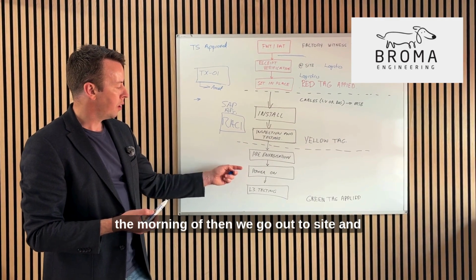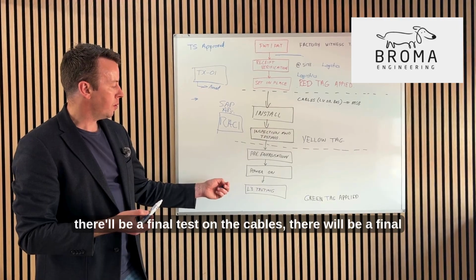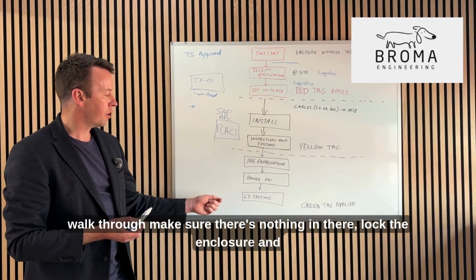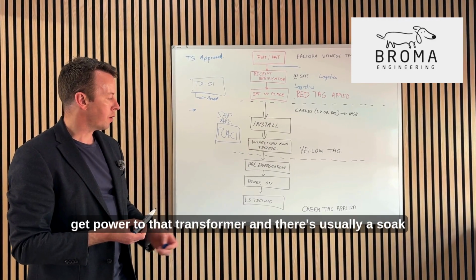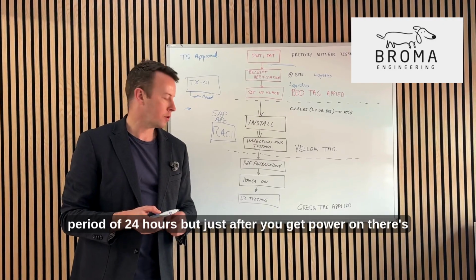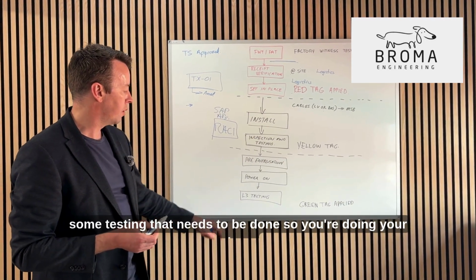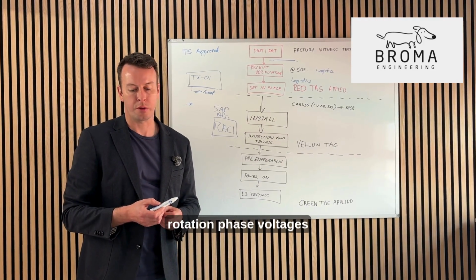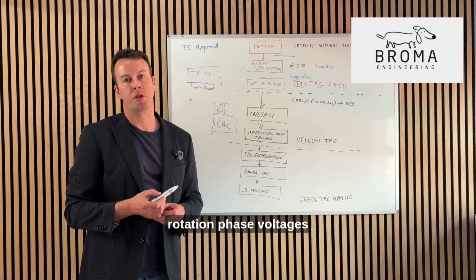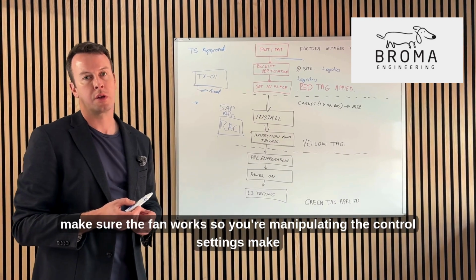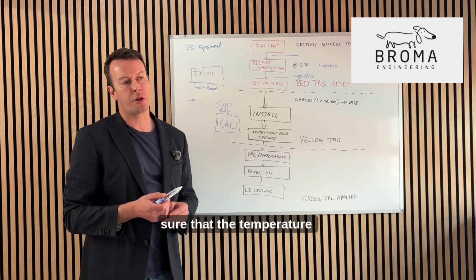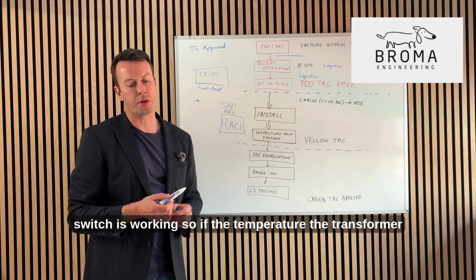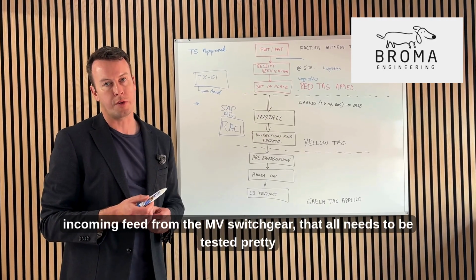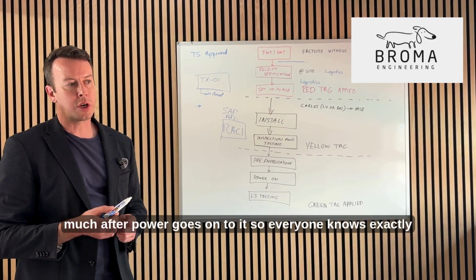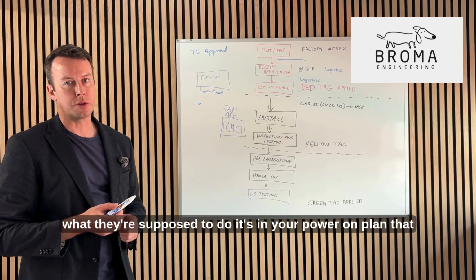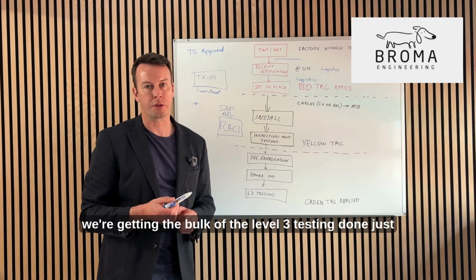And then on the day, usually do this pre-energization meeting the evening before and the morning of. And then we go out to site, and there'll be a final test on the cables. There'll be a final walkthrough, make sure there's nothing in there, lock the enclosure, and get power to that transformer. And there's usually a soak period of 24 hours, but just after you get power on, there's some testing that needs to be done. So you're doing your phase rotation, phase voltages, make sure the fan works, so you're manipulating the control settings, make sure that the temperature switch is working. So if the temperature of the transformer goes too high, that'll kill the incoming feed from the MV switchgear.